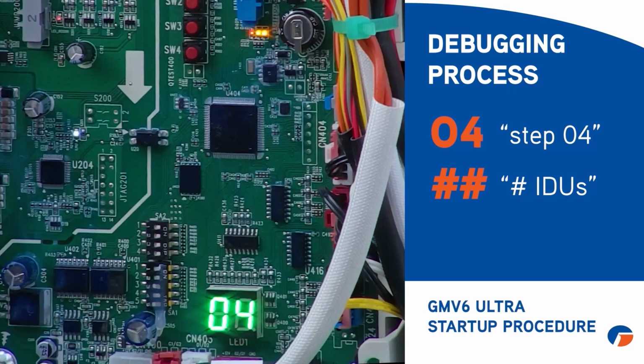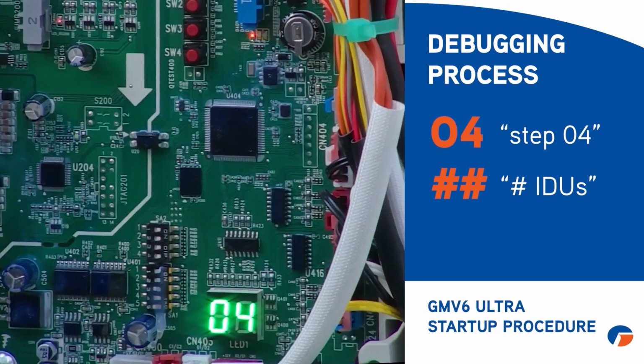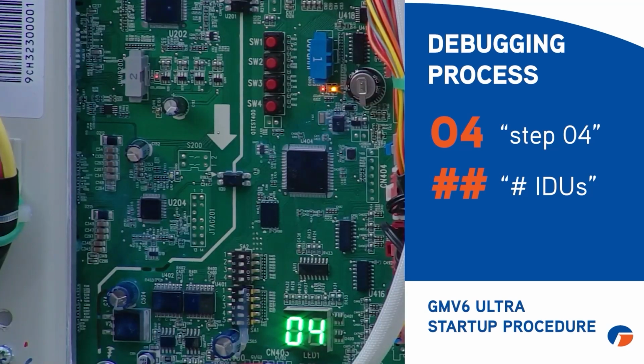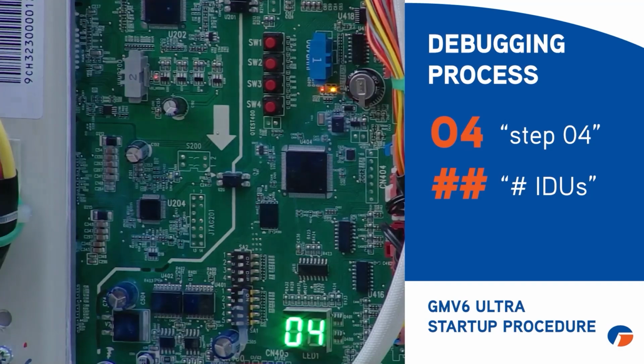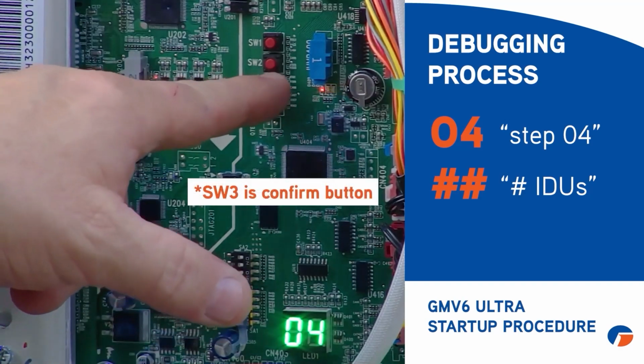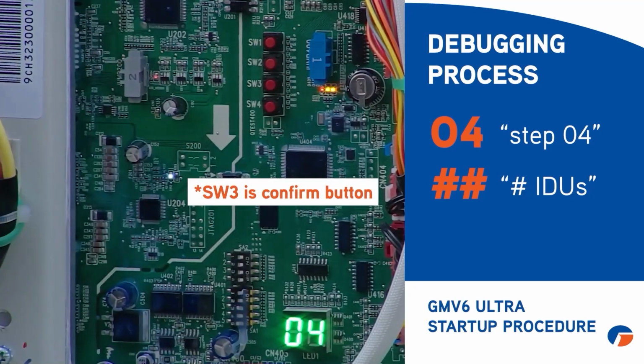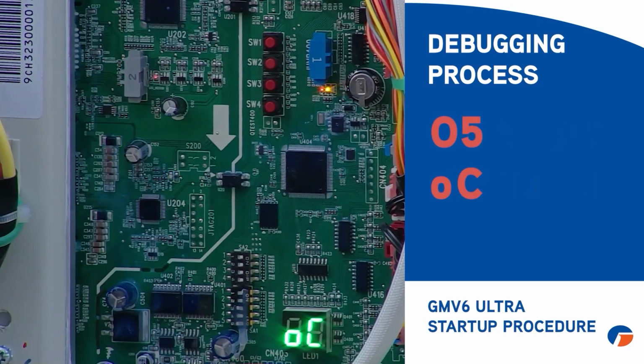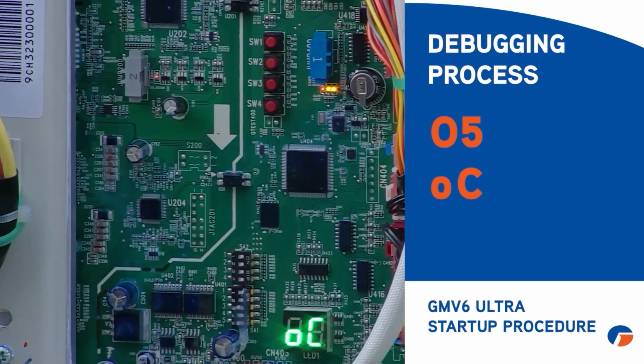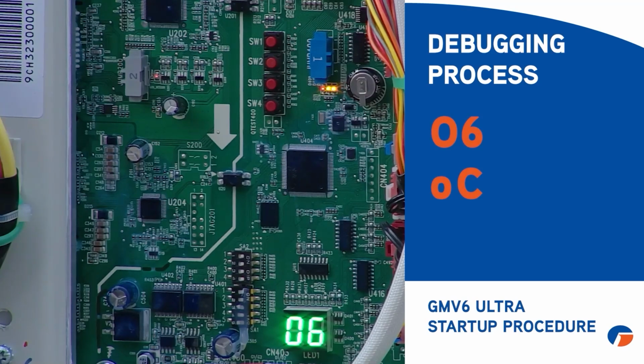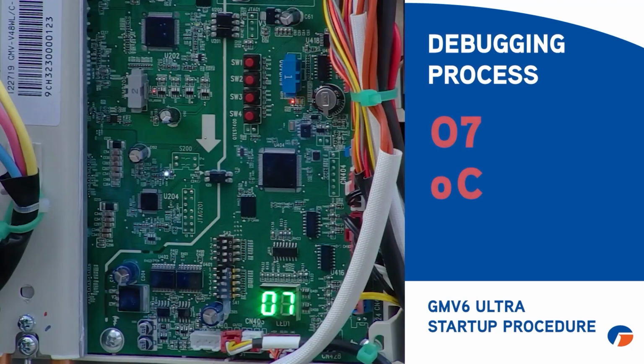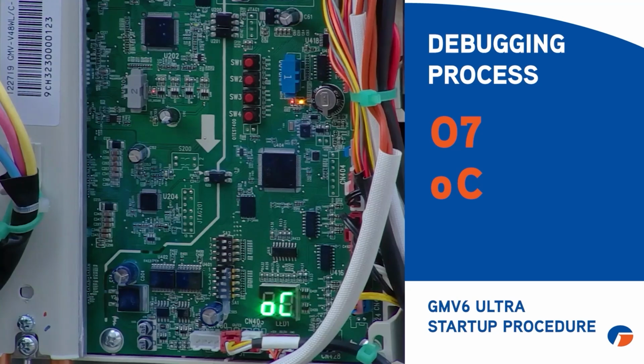04. Since it's the same, it just says 04, because normally it would say 04, 04, 04, 04, which means step 4, 4 indoor units. But I guess because it's the same, it's not bouncing. I know I have 4 indoor units, so I can just hit SW3 one time and confirm it, and it should move on. Yep, step 5, step 6, and you just got to let it do its thing. There it goes, going to 07. So now it's in step 7.